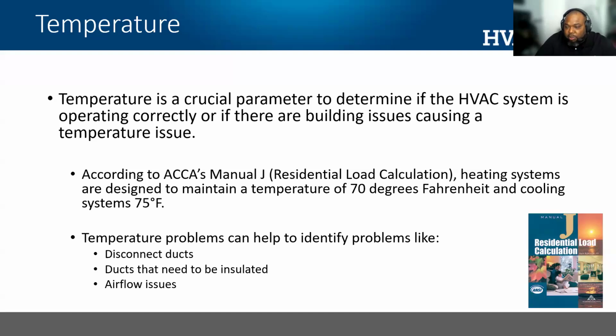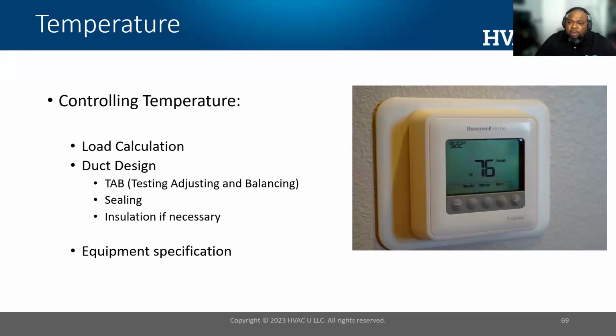So, in our business, we follow ACCA Manual J's process for designing heating and cooling systems to maintain appropriate temperatures, and we measure temperature as a way to verify that the HVAC system is working. So controlling temperature, our process: we do a load calc where we properly size the equipment to meet the needs of that home. We do equipment specification, and then we do a duct design to make sure that the energy we size the heating and cooling equipment for has the ability to get out into the house or building and adequately heat or cool that building. Measuring temperature helps us to identify that the system is working and we're not contributing to the IAQ problem by having a poorly designed or operating system.